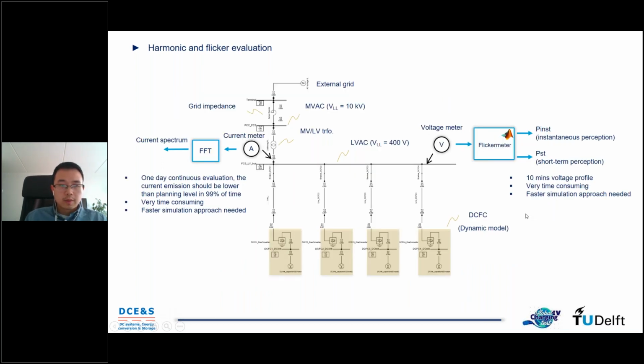Once you have the model of the chargers and the grids, you can develop a charging station impedance model. And if you also have the load profile, or charging profile of the chargers, you can evaluate the harmonics once you get the current at the PCC point. You may also evaluate the flicker if you get the voltage at the PCC point.